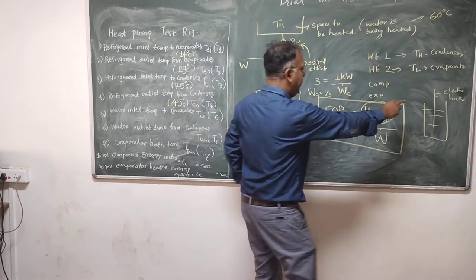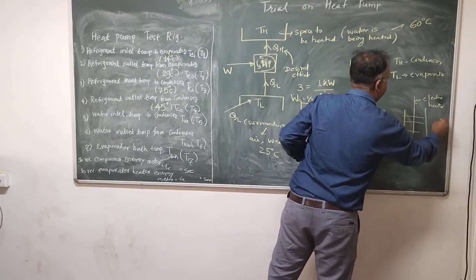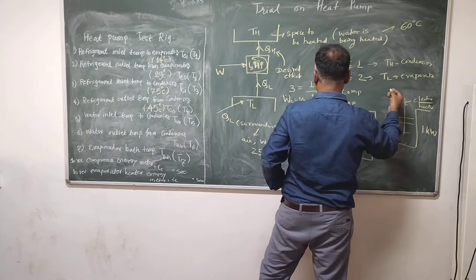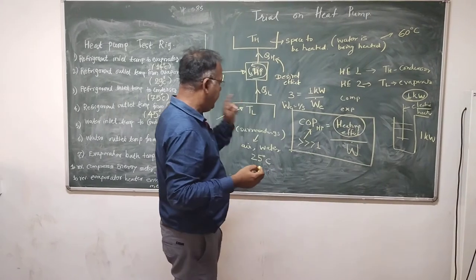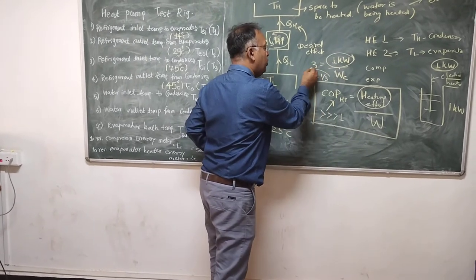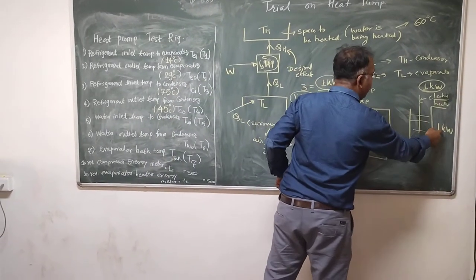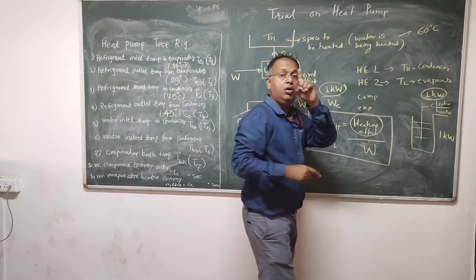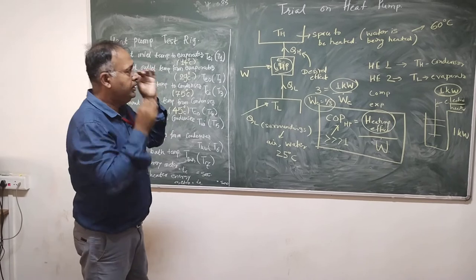If you are using an electric heater and you want to achieve a heating effect of 1 kilowatt, even assuming 100 percent efficiency, you would require an electric heater of 1 kilowatt capacity. So for achieving the heating effect of 1 kilowatt, the heat pump would consume only 1/3 kilowatt, whereas the electric heater would consume 3 times more — 1 kilowatt against 1/3 kilowatt. This is the basic concept of the heat pump.